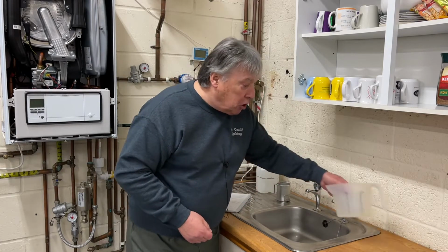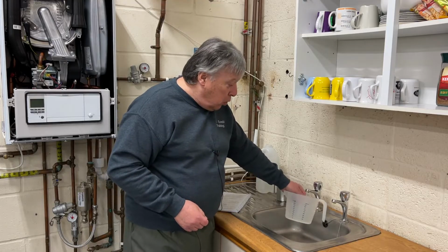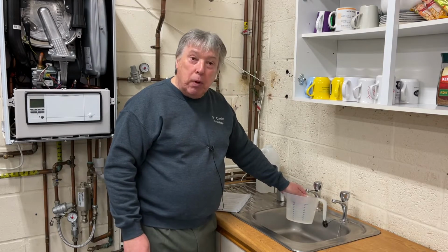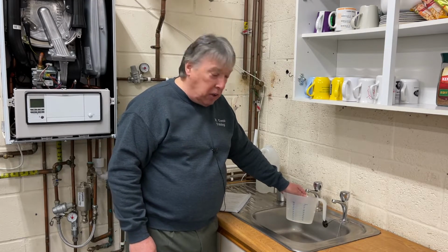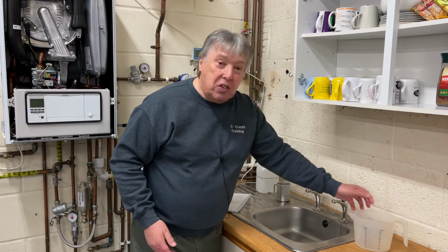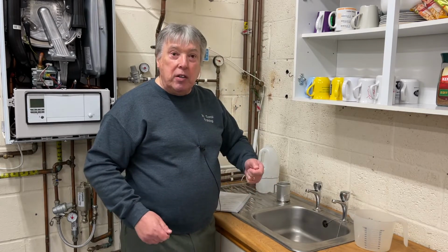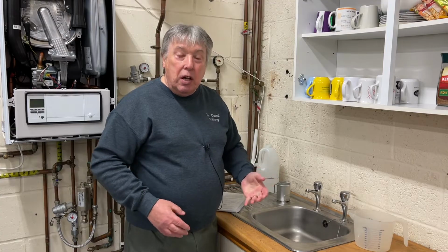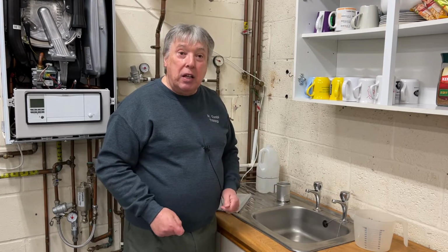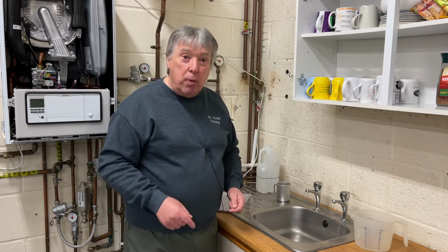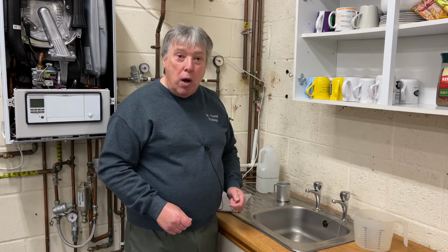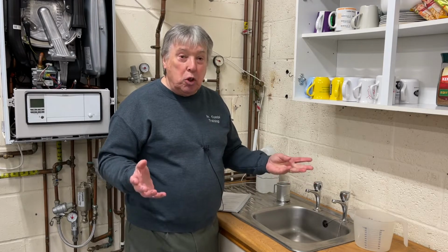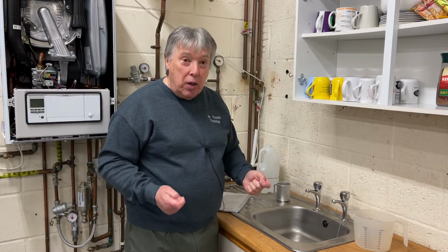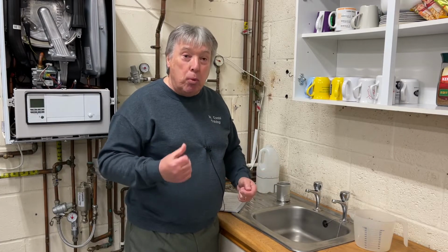If we go back to the jug here again, all we do there is count how many seconds it takes to 1 litre. For example, if it takes 6 seconds divided into 1 minute, 60 is 10. So that would be a 10 litre flow rate. And if that corresponds with the manufacturer's requirements, that's perfect. That's how it should be. But if it's a lot lower than that, then something is wrong inside the boiler.